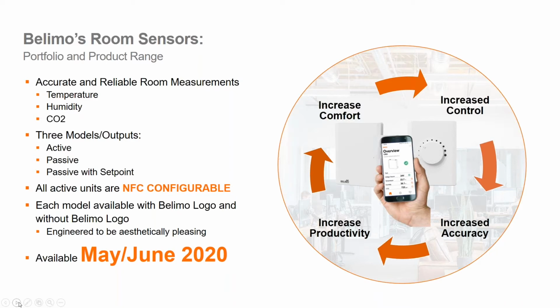The NFC app outputs you could choose from would be 0 to 5 volt, 0 to 10 volt, 2 to 10 volts, and of course the MP bus that's specific for Belimo. The three types of measurements our room sensors will be able to measure are temperature, humidity, and CO2.